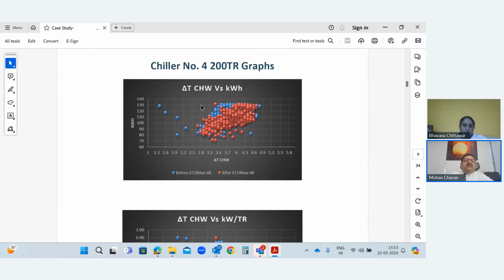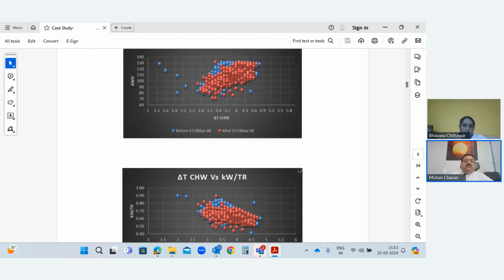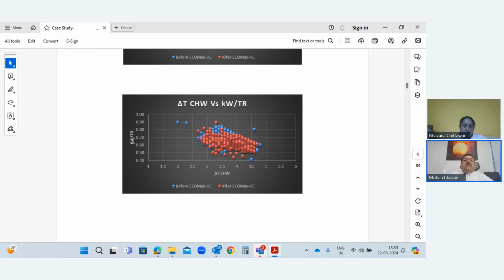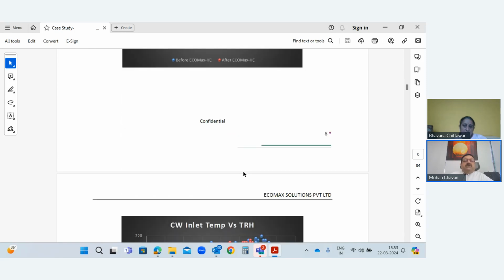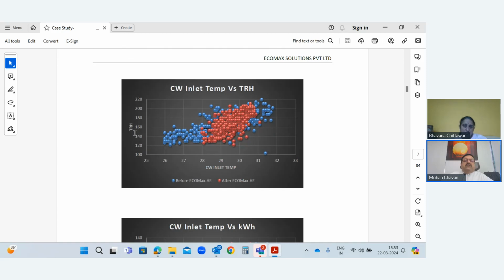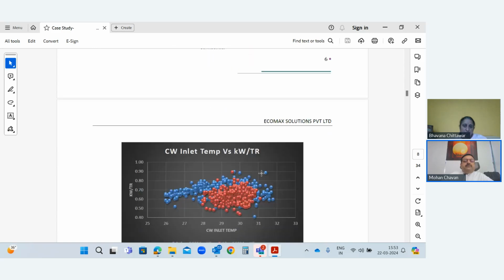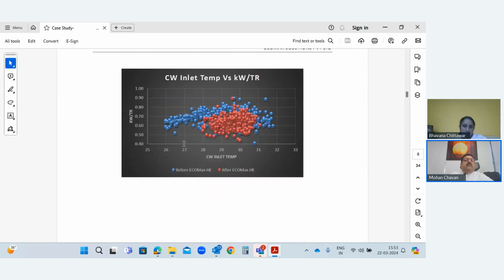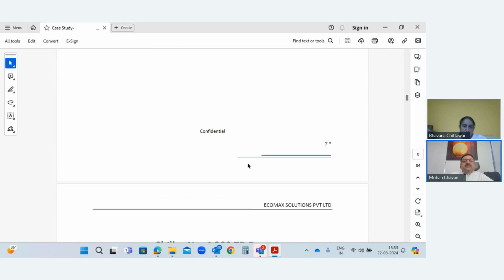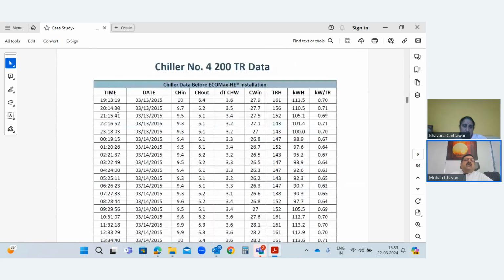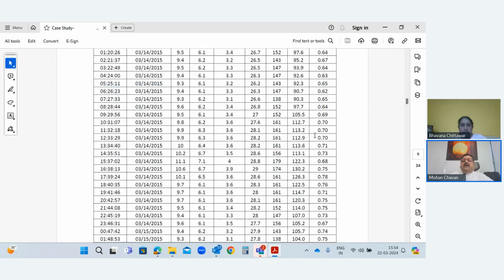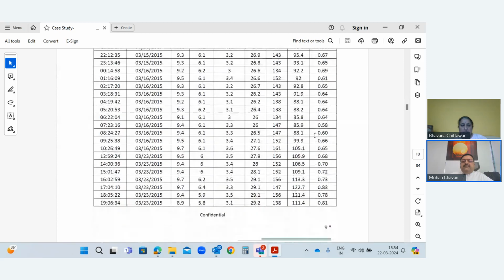And these are some of the trends that we plotted: kWh versus chill water temperature. Then kW per TR versus chill water temperature. This is TRH, that is cooling generated versus CW inlet temperature. Again, kilowatt versus CW inlet temperature. And this is the backup data wherein we had installed a data logger there for measuring all these parameters. Okay, chill water in, chill water out, then TRH, kWh, and that's where we monitored the IKW per TR.